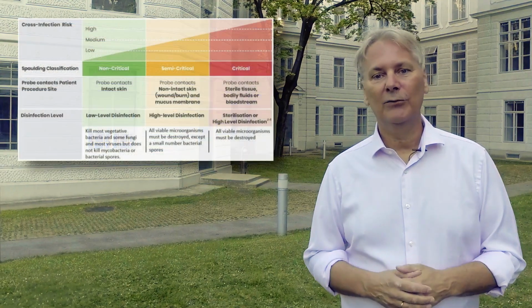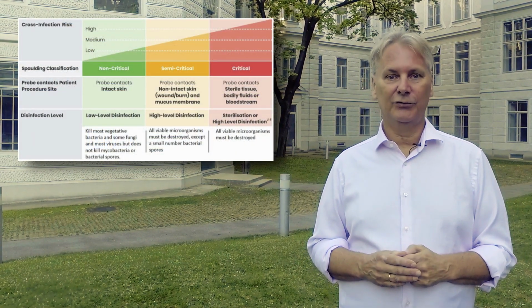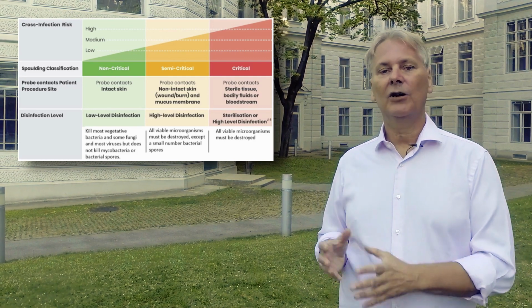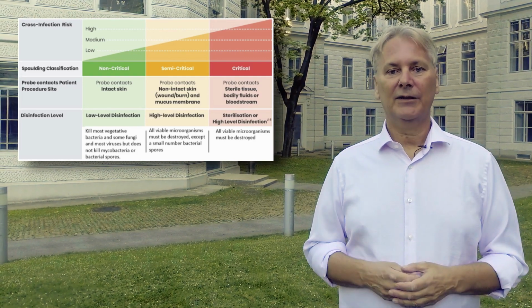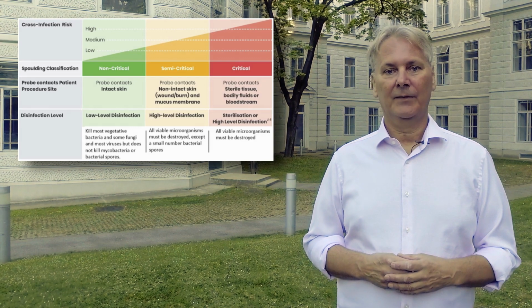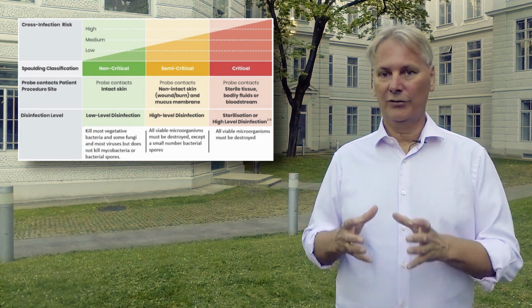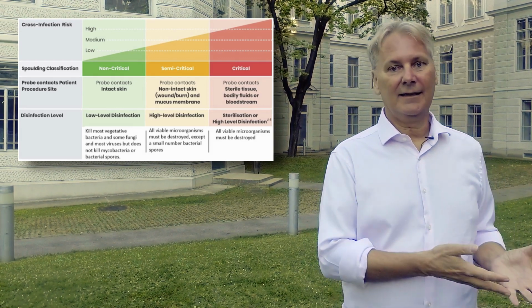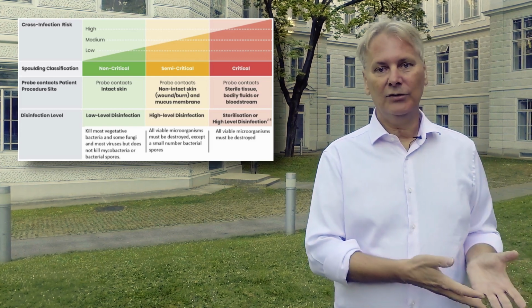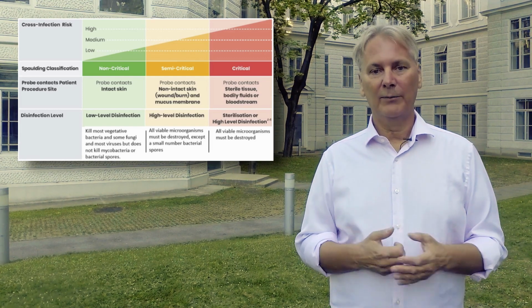But how do we determine which level of disinfection we should choose? Low, medium, or high? That depends pretty much on the so-called germicidal activity. You have to check whether your probe or instrument was in contact with intact skin, an infected wound, the mucosa, or the bloodstream.